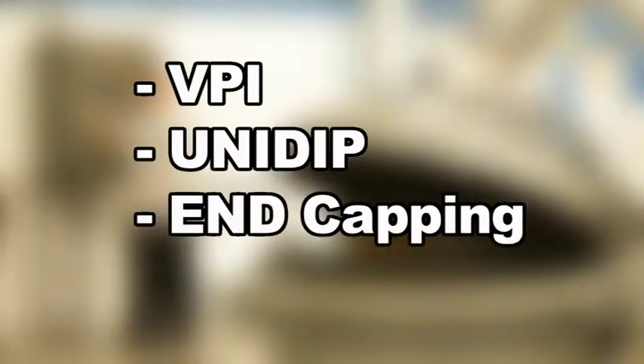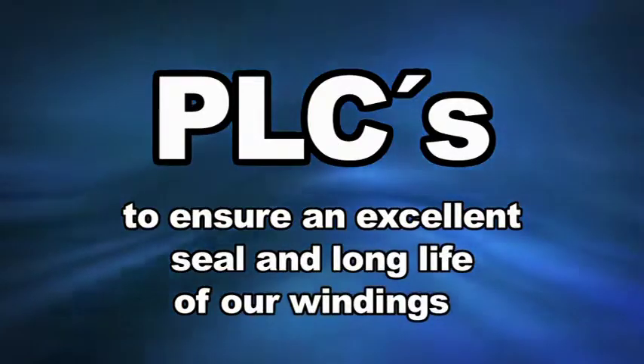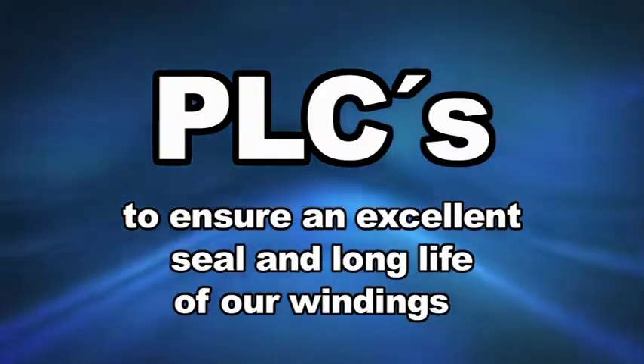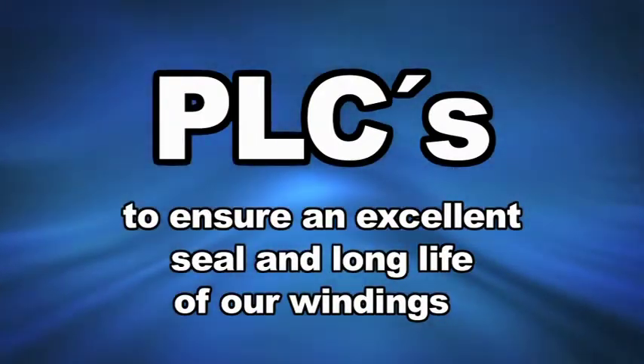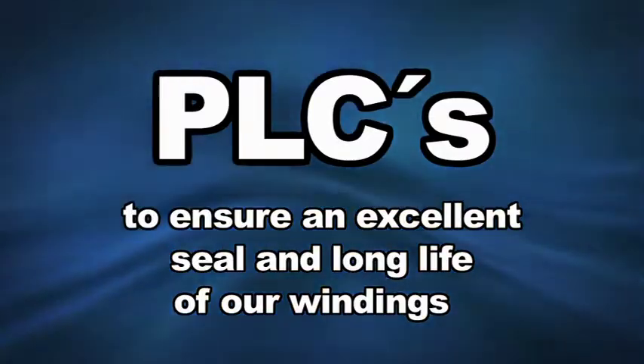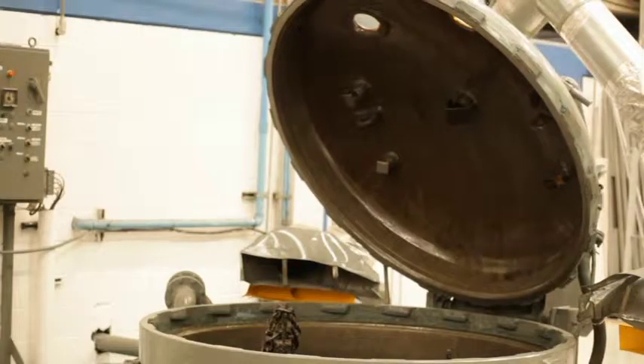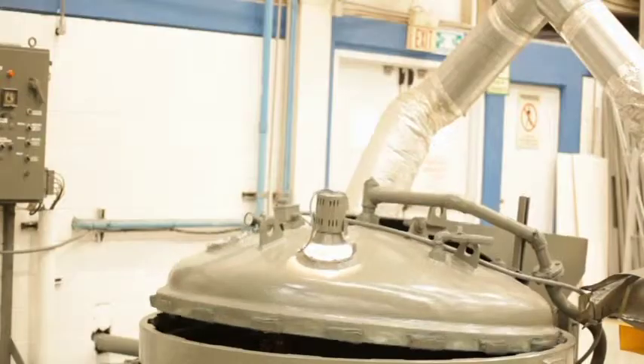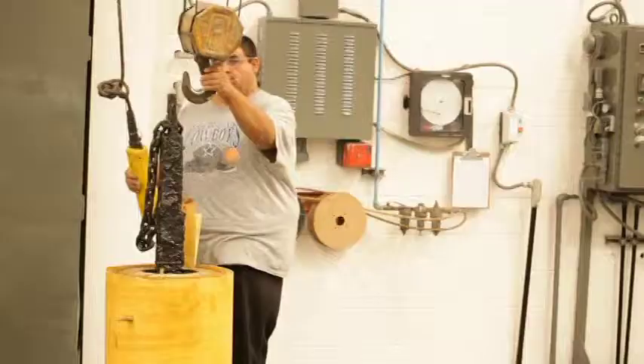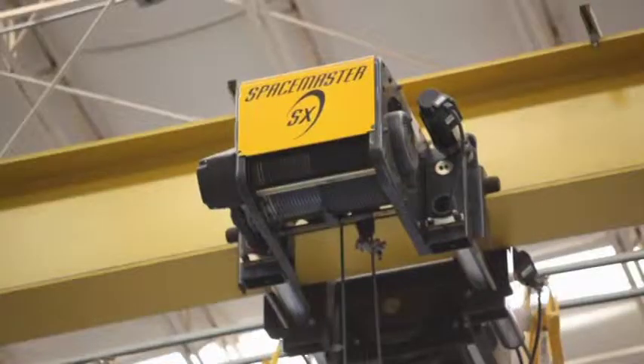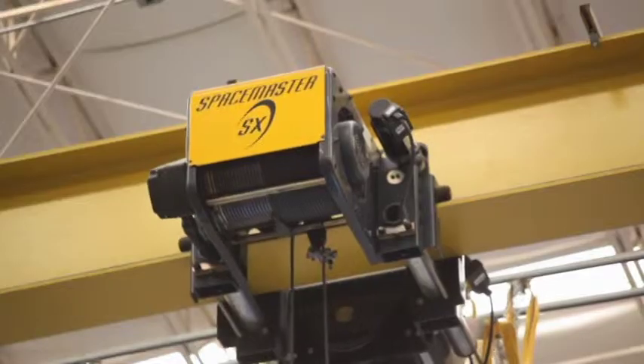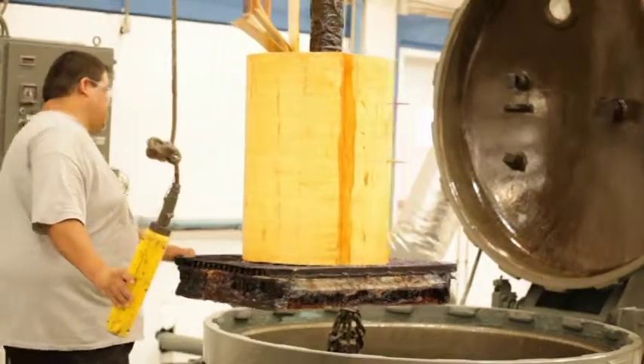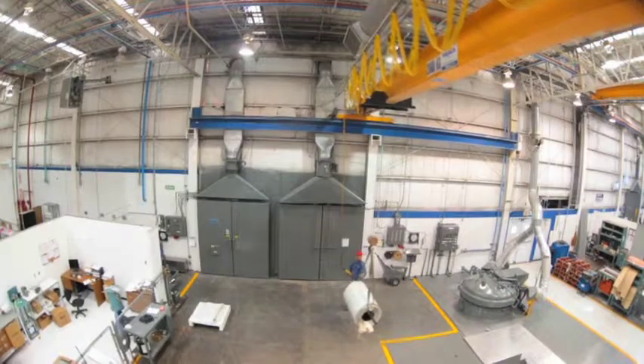Encapsulation procedures such as BPI, Unidip, end capping, and Uniclad are strictly controlled by PLCs in times and temperatures to ensure an excellent seal and long life of our windings. The VPI process consists of removing moisture from the materials at high vacuum and then proceeding to impregnate the coil with a special epoxy resin. It then proceeds to cure or solidify the resin in ovens at high temperature.